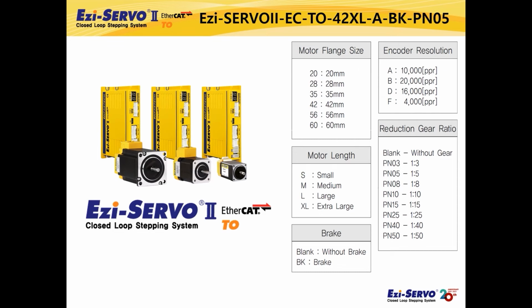First of all, I will explain the combination model name of Ezi-SERVO II EtherCAT TO product. In the example model name, EC means the product using the EtherCAT network, and TO means that the product has the torque off function. 42 means 42 mm motor flange size, and XL means motor length. A means a product with 10,000 ppr encoder applied. BK means that a brake is attached on the motor, and PN05 means that a planetary gearbox with a gear ratio of 1:5 is attached on the motor.